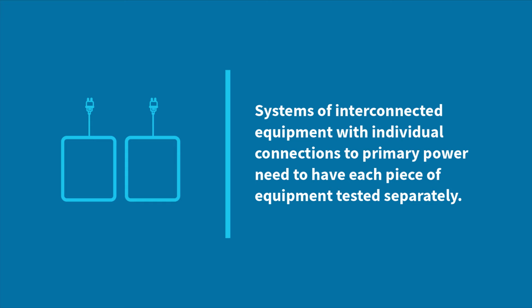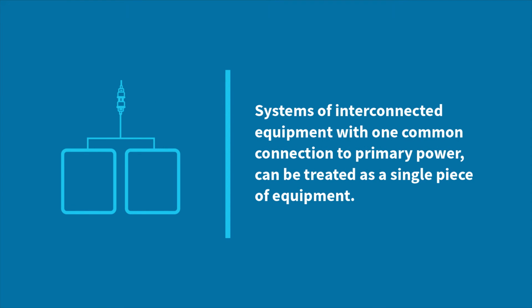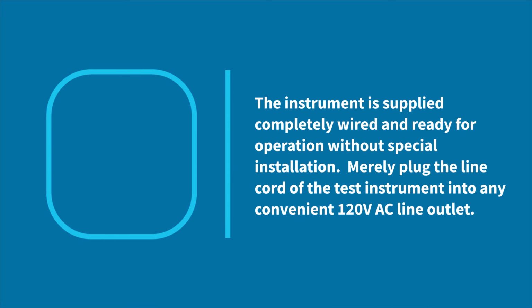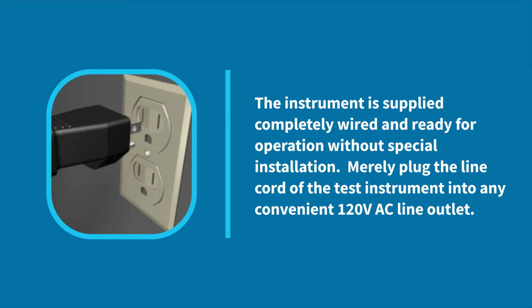Systems of interconnected equipment with individual connections to primary power need to have each piece of equipment tested separately. Systems of interconnected equipment with one common connection to primary power can be treated as a single piece of equipment. The instrument is supplied completely wired and ready for operation without special installation.